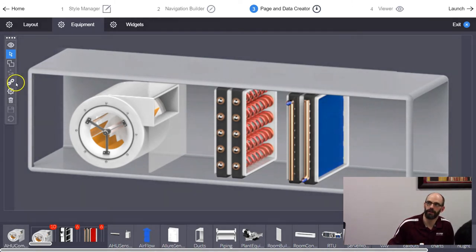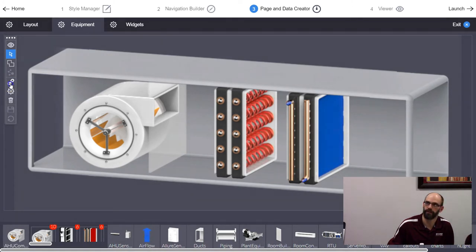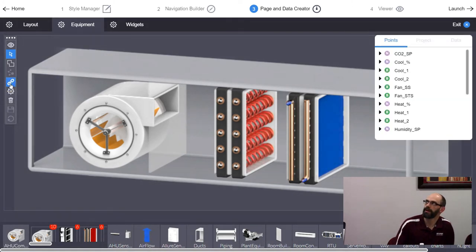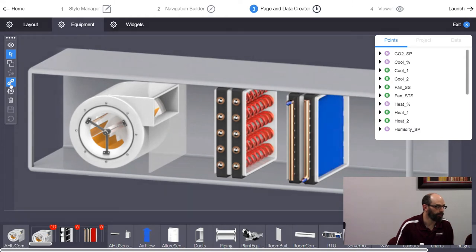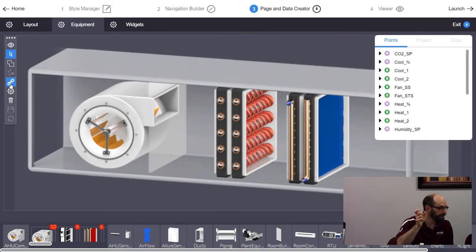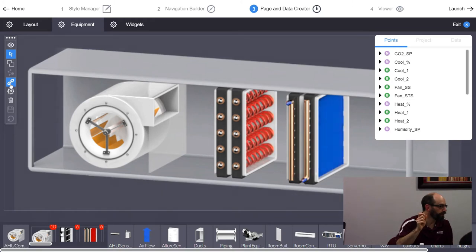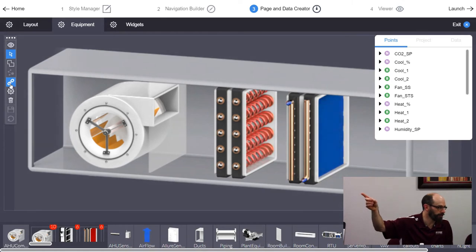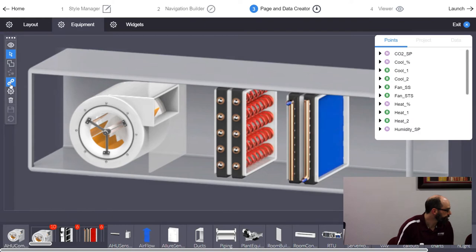Since we're animating equipment, we use the binding dialog — the link icon. Click it and it pops up the points on the right-hand side. The points you see are from whatever key controller you set earlier. If you had set Controller 2 as your key, you'd see Controller 2's points instead of Controller 1's. You're only building the graphic based on the key controller's points.